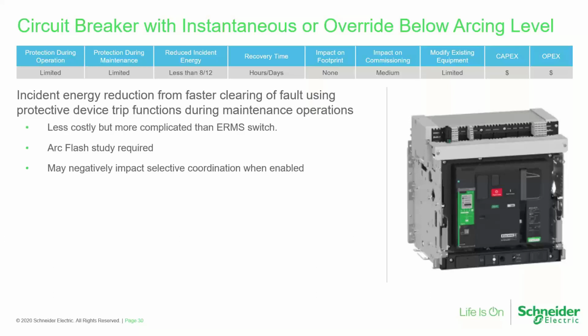Well, the maintenance switch is one of those things that it's almost a no-brainer, right? You turn it on, maybe you're dropping your instantaneous trip down to a minimum level. We know that's going to give us pretty good protection. With this, we're actually having to do an arc flash study. We're having to look at different system operating configurations to make sure that we get that trip level in below the available arcing current.